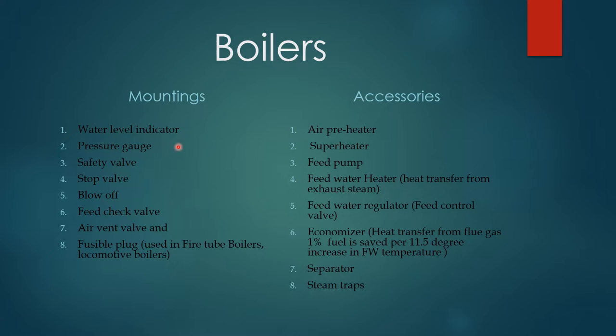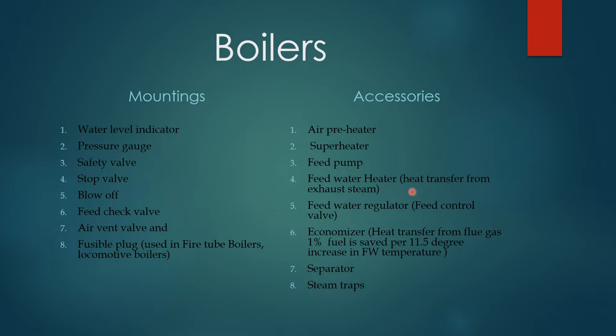The mountings include: water level indicator, pressure gauge, drum pressure gauge, pressure safety valve, main steam stop valve, blow-off valve, feed check valve, air vent valve, and fusible plug — normally used in fire tube or locomotive boilers. Accessories include air preheater, superheater, feed water pump, and feed water heater, where heat transfer is from exhaust steam.